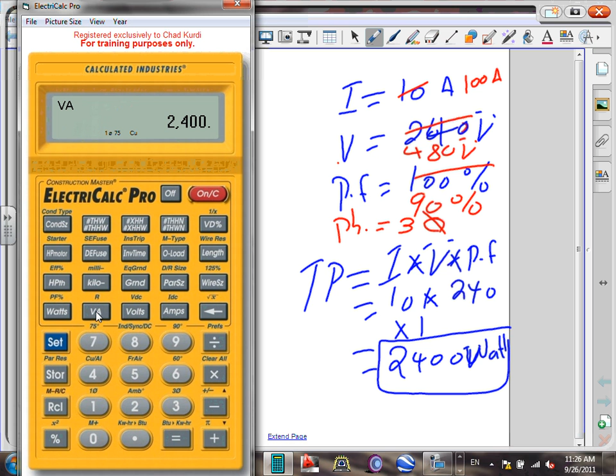Let's take another example related to the same topic. I'm going to change this one, guys, into 100 amp, 480 volt, 90% power factor, and change the phase into three phase. So now I have 100 amp, 480 volt, three phase, power factor of 90, and I need to find something.